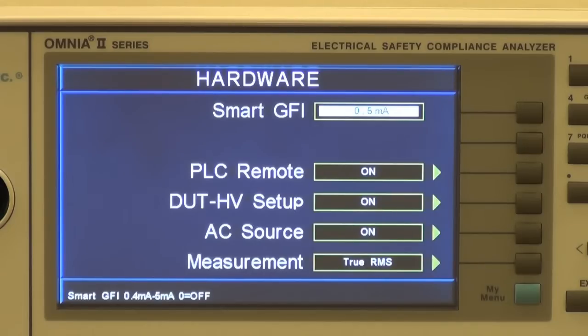The DUT/HV selection activates an additional parameter in the AC or DC withstand and IR test parameter screens. The additional parameter is called DUT output, and its function is to control the high voltage relay at the DUT output. When the DUT output parameter is turned on during the AC or DC withstand and IR test, high voltage will be present at the DUT output as well as the front and rear panel output terminals. When the DUT output parameter is turned off, no high voltage will be present at the DUT connectors, only from the front and rear panel outputs.